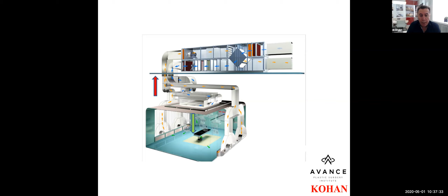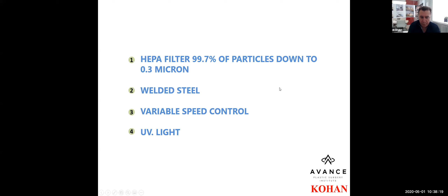These HEPA filters clean about 99.7% of particles down to about 0.3 microns, so they really clean the space. That's why we use them in hospitals, in ORs, in those negative pressure rooms you've probably seen with signs on them. We also recommend UV lights in every practice these days. And welded steel ductwork is a big deal too, because it's costly and different from the kind of ductwork you presently have in your practices.